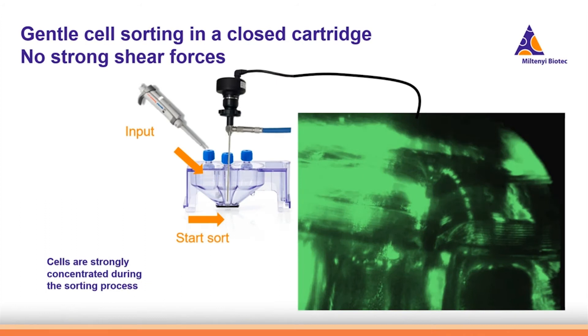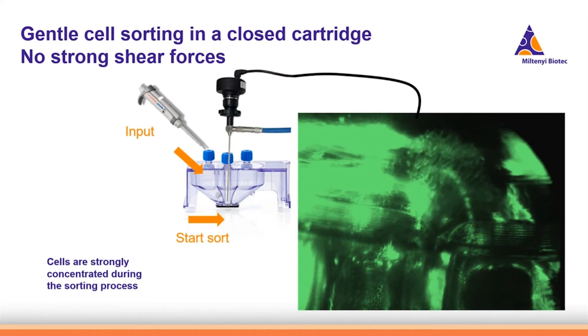Let's have a look at how the cells arrive in the positive collection chamber. An endoscope was inserted into the positive collection chamber, the cartridge was loaded, and sorting was started. We can see that the cells are easily flying into the positive collection chamber. Another advantage is that cells are strongly concentrated during the sorting process because the valve only opens for the short time the cell needs to be sorted, which can save you a centrifugation step.